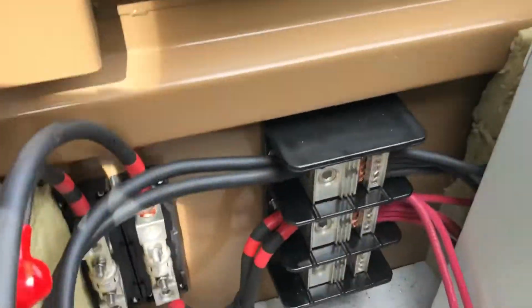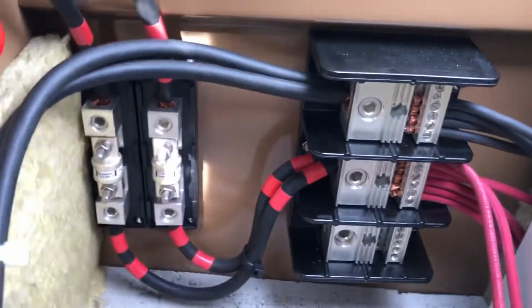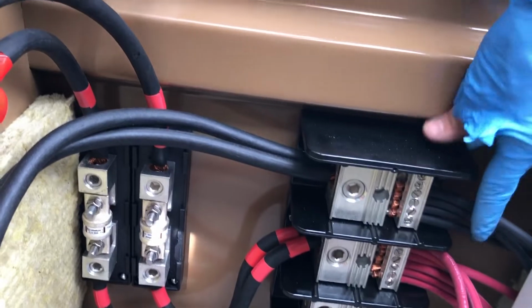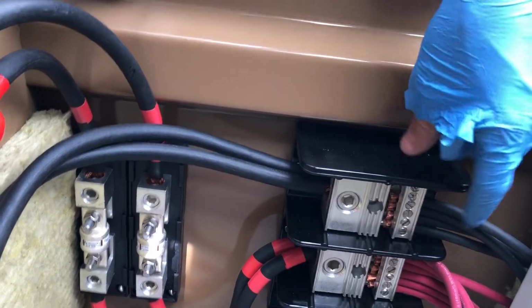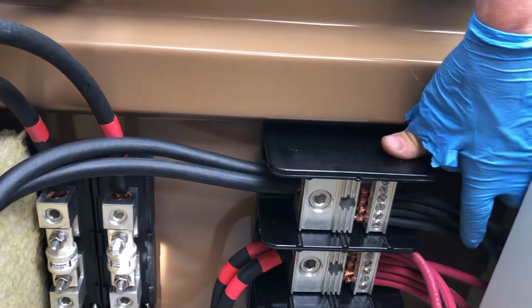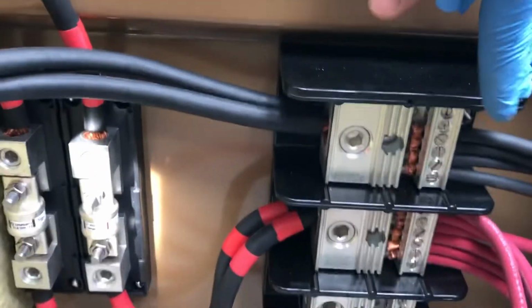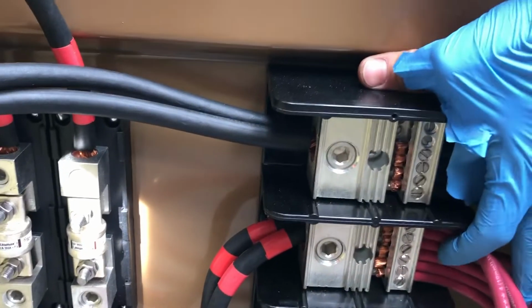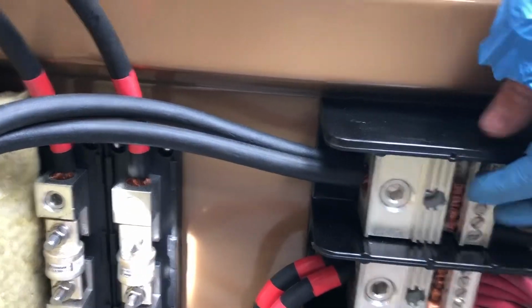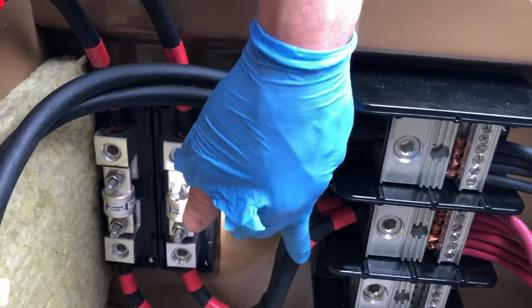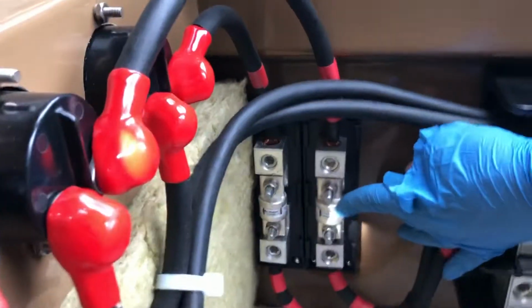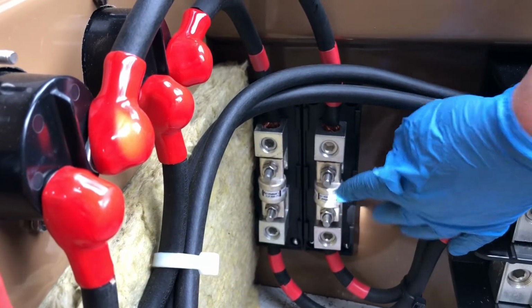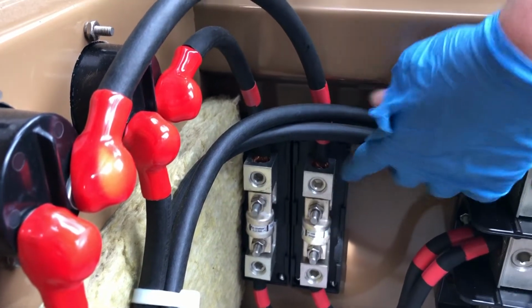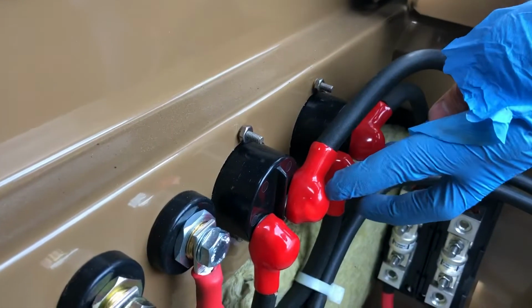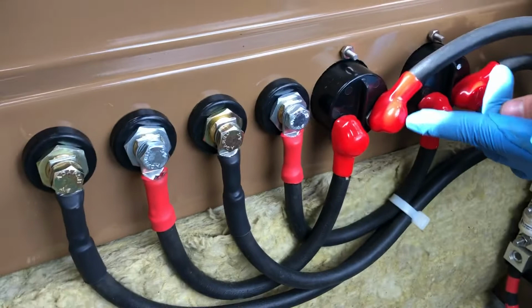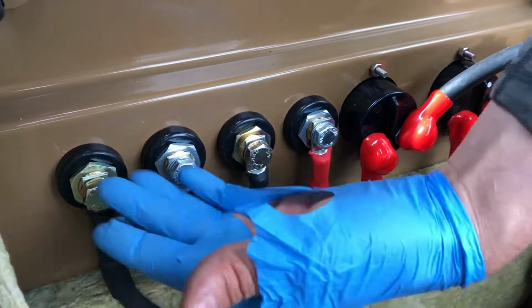So here I put in a little power distribution block. All of the batteries have equal length conductors, and they all come to this terminus and are combined in this block. Then I have 2 parallel outputs that go to 2 200 amp class D fuses, then to these circuit breakers, and the output of the circuit breakers goes to the outputs that leave the case.